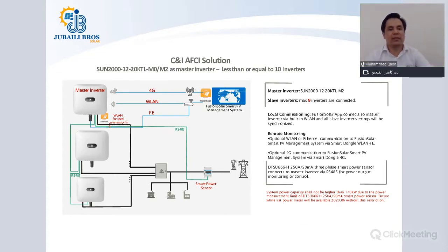If you have the AFCI solution requirement with a medium scale project, and you are using a 12 to 20 kilowatt size as a master inverter, in that scenario you can use a dongle, and local commissioning can happen through the FusionSolar app. Remote monitoring can happen again with the FusionSolar app or the web monitoring platform. For the remote monitoring, either dongle can be used, either the WLAN-FE or the 4G dongle type. Power sensor you can use from Huawei itself.